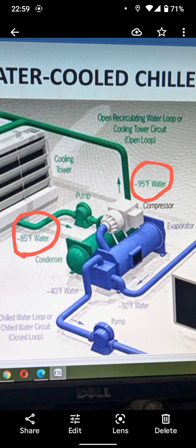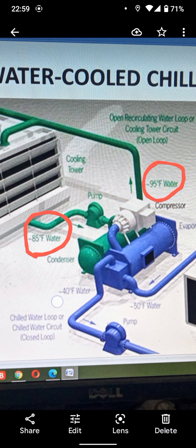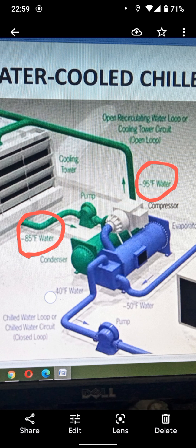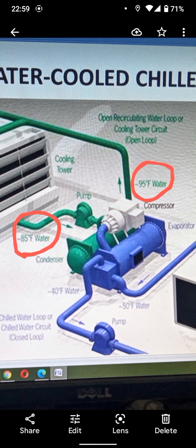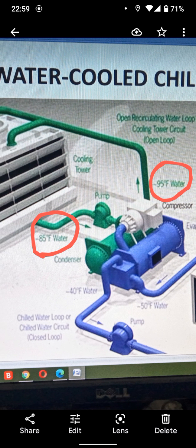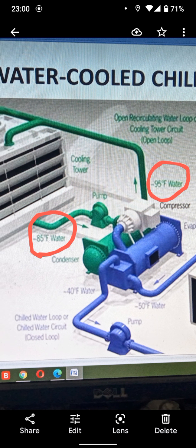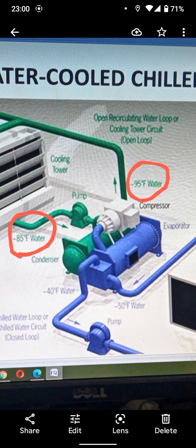In this situation, the end user wanted to run the chiller immediately because they had completed the installation. The installation party had the same intention, and my management also. This is not my fault, it is not anybody's fault. It is a design problem. Who approved that the cooling tower should be inside the boundary and not get fresh air? At this stage there was too much tension on the startup commissioning party, end user, sales department, and maintenance department. Everybody was disturbed. You cannot decrease 90 Fahrenheit to 85 Fahrenheit because of this reason. And if you run four cooling towers, what happens? Can the temperature drop to 85 Fahrenheit? Can you do this?